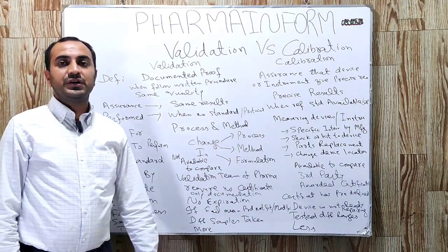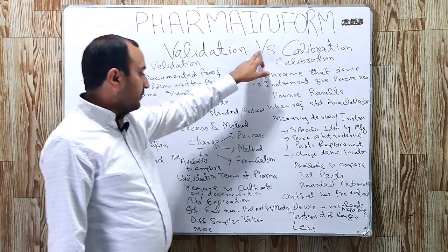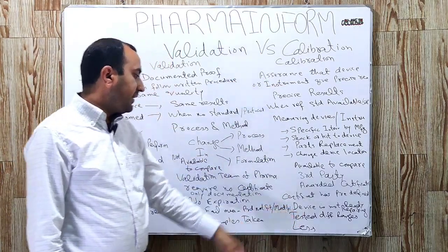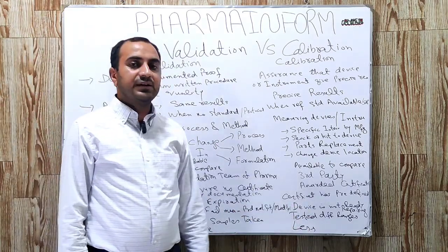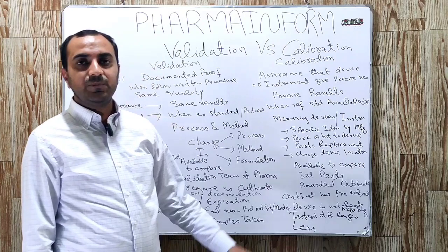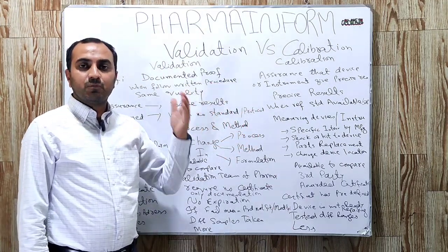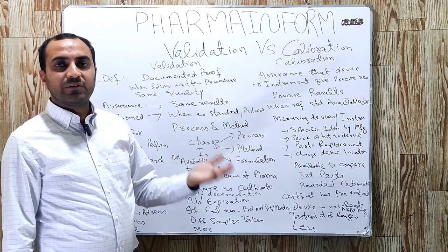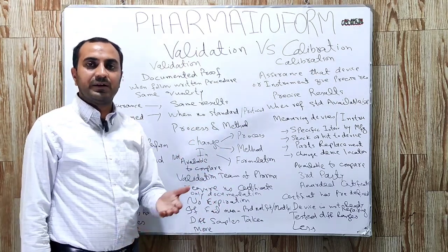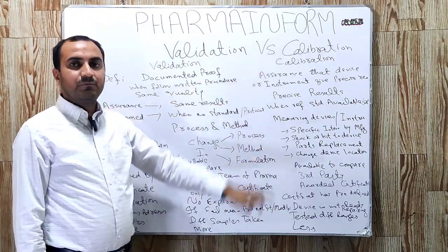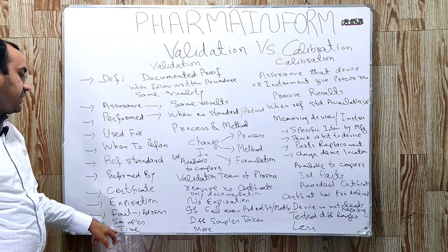Regarding samples: in validation, we take different samples at different time intervals. In calibration, we do not take any samples. Instead, the device is tested against different ranges. For example, with a weighing balance, we put weights of 5 kg, then 10 kg, 15 kg, and 20 kg, depending on the capacity of the balance.